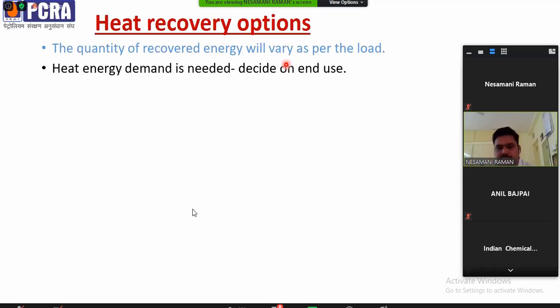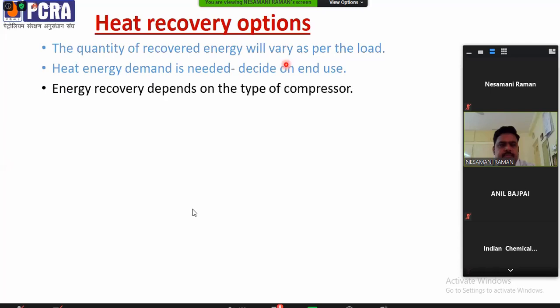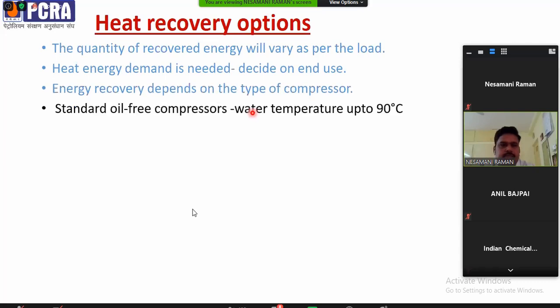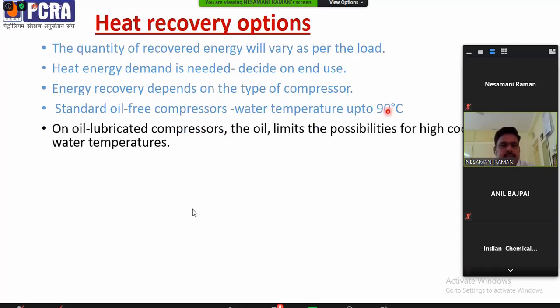Before finalizing a heat recovery plan, we have to find the demand. Whether we need boiler feed water or any other heat demand, for example for a cooling system. Do we have a constant demand for heat? Then only we can install this heat recovery option. The heat recovery quantity will also vary as per the type of compressor. Standard oil-free compressors are best suited for applying heat recovery, because they generate water temperatures of up to 90 degrees Celsius, which can be used as boiler feed water or for any other purpose.